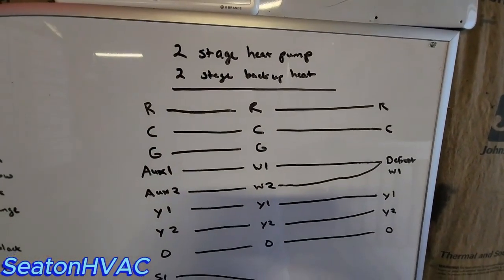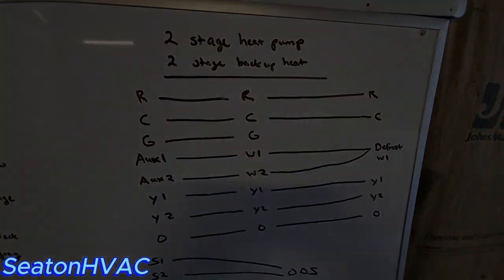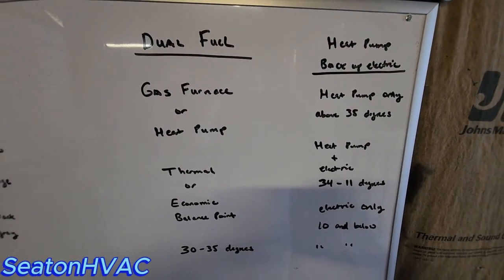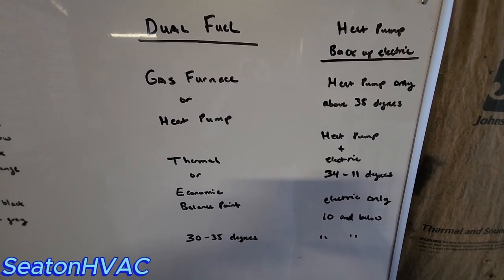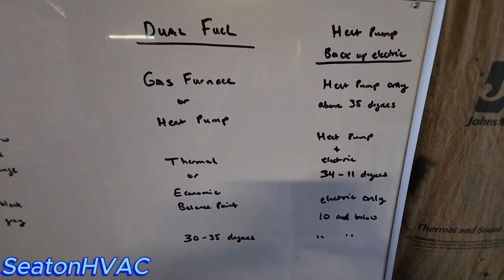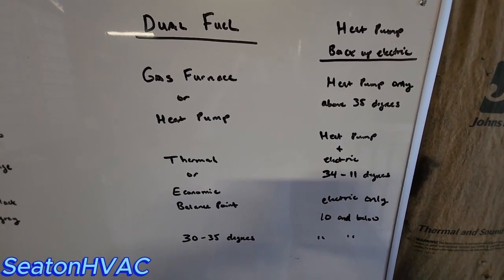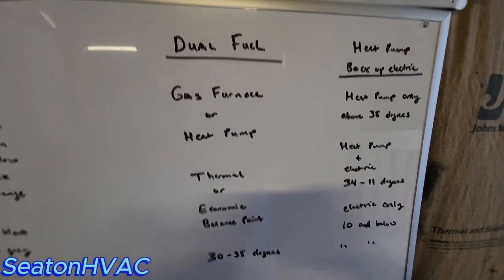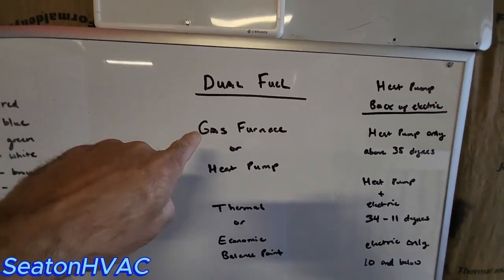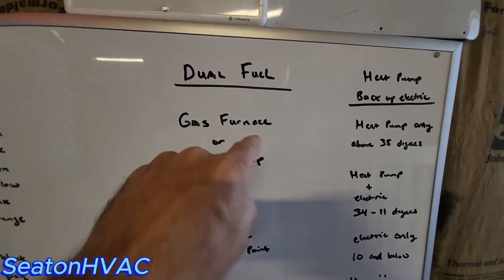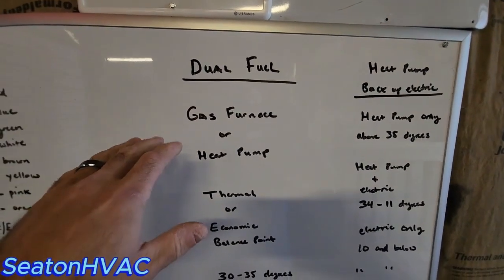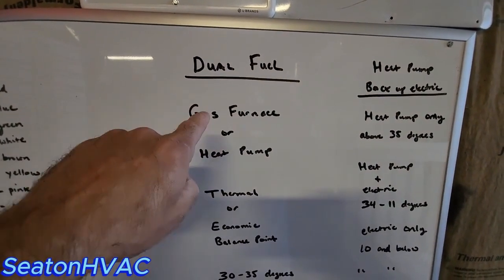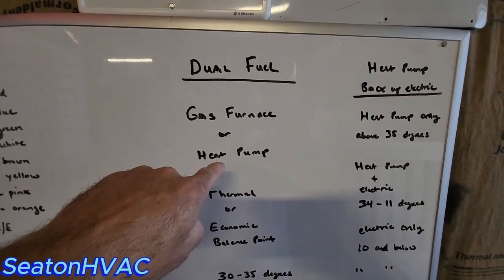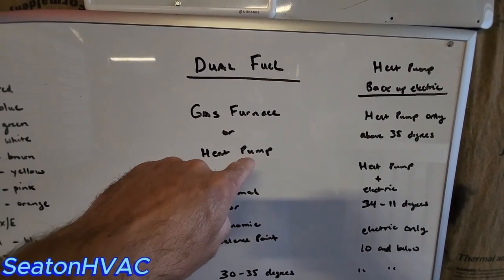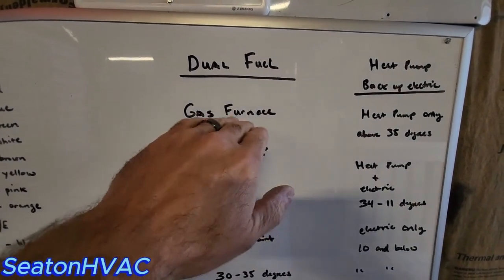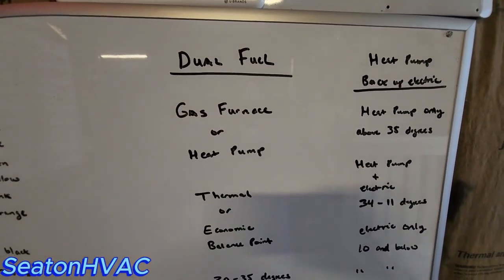So how about a dual fuel? How would we set that up? Okay, guys, instead of showing you the wiring for these, I'm going to show you the difference, because the wiring on a dual fuel as opposed to a heat pump are pretty similar. So I won't be going over things too much. On a dual fuel system, it's going to be your gas furnace or your heat pump. They'll never run at the same time. They can't, because your gas furnace will actually cause your heat pump to go out on high head pressure if you had the heat pump run at the same time. So you run the heat pump down to a certain temperature, then it switches over to your gas furnace, okay?